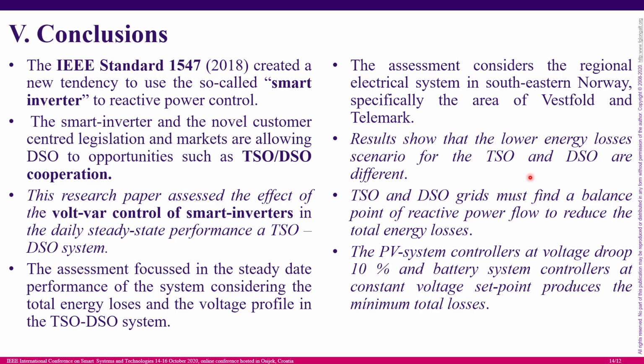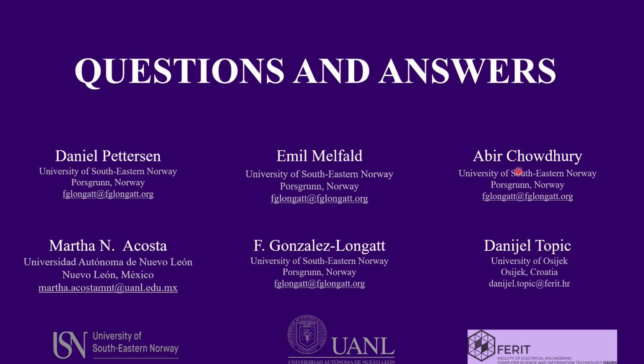Finally, after the careful assessment of the whole set of results, and this paper has many results, we identified that the PV system controller set to voltage droop with 10% and a battery energy storage controller with a constant voltage setup produce the minimum total losses in this system. Okay. Well, this is all for this paper.